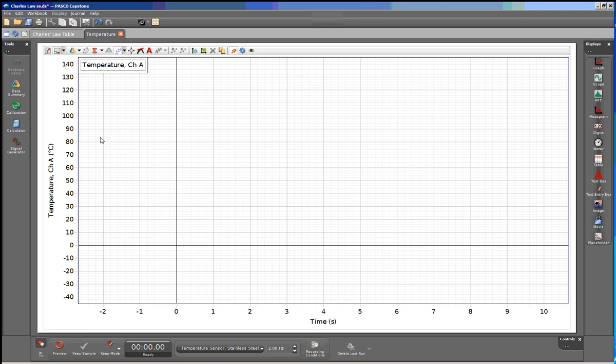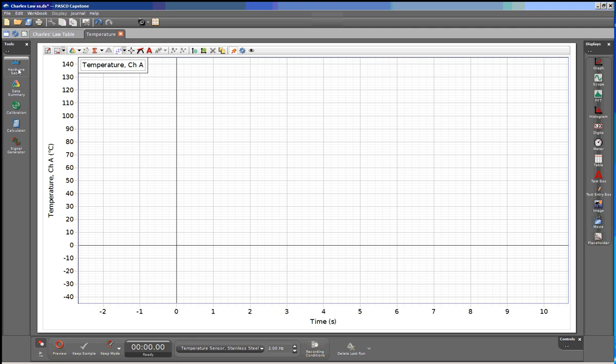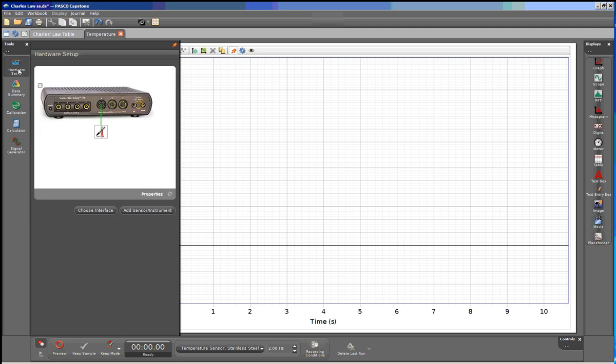I can also check to make sure this is properly configured by clicking on the Hardware Setup button. So you can see we have a picture of the 750 interface, and it has assigned a stainless steel temperature probe to channel A.